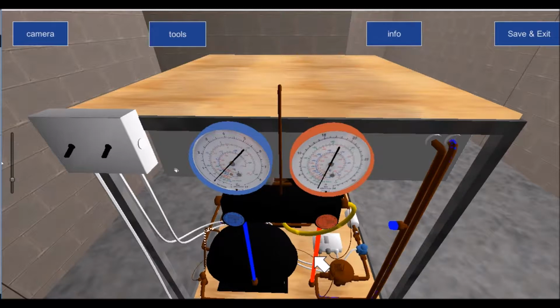Now, the other key message that I need to get across tonight is how the gauges actually operate. It's very important that you understand how the gauges operate. There is a YouTube video out there where I've taken the back cover off and shown you how a Bourdon tube gauge actually works. What I'm trying to do here tonight is explain the importance of understanding when these valves should be open and when they should be closed, so that you don't make the mistake of inadvertently allowing refrigerant to escape to the atmosphere, or inadvertently allowing high pressure to go across to low pressure when you're trying to diagnose a problem with the system. And also to help you understand how to remove gauges from a system without losing refrigerant to the atmosphere. So we'll start by explaining how they operate.